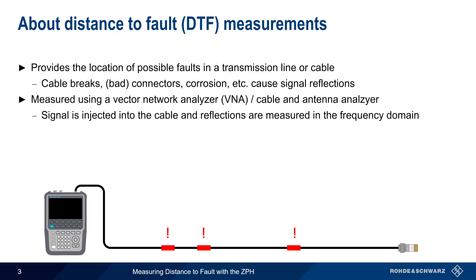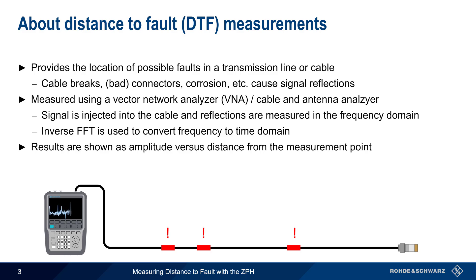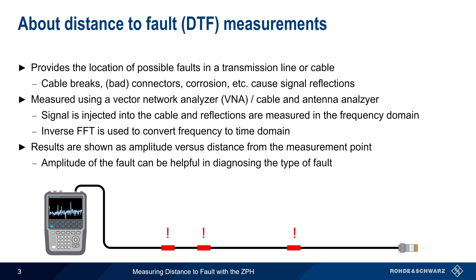At a high level, this is done by injecting a signal into the cable under test, and then measuring the reflections in the frequency domain. An inverse fast Fourier transform, or IFFT, is used to convert this frequency domain information into the time domain. These time domain results are plotted as amplitude versus distance from the measurement point. In some cases, the relative amplitude of the fault can also provide information as to the nature of the fault, or the cause of the reflection.